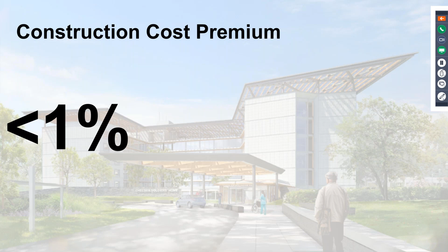BU Center for Computing and Data Sciences is a 350,000 square foot, 20-story high-rise in construction right now in Boston. Similar to Chelsea, the entire bore field has been drilled. It uses 31 boreholes, each 1,500 feet deep, with a concentric pipe-within-a-pipe system to handle the pressure in that configuration. We're targeting a 40 EUI for a building that runs from 5 a.m. to 11 p.m.